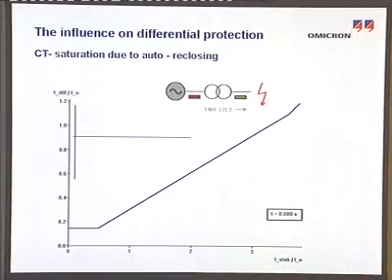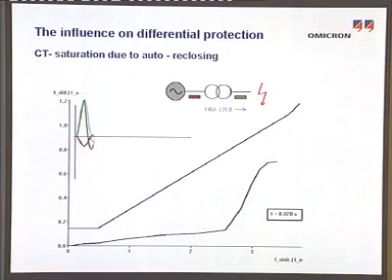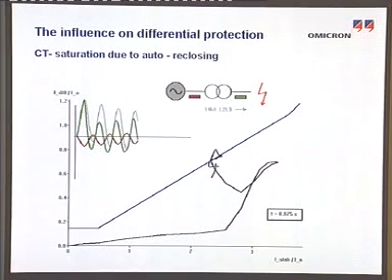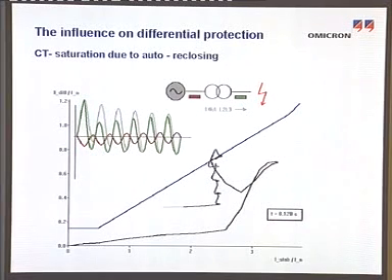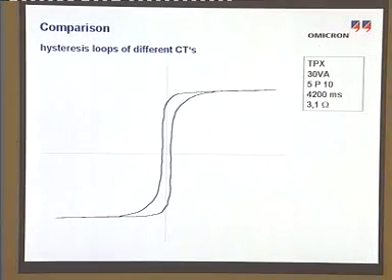If the relay behavior is also examined offline at re-closure, the simulation shows that the stabilizing characteristic is exceeded in the second area due to smaller stabilizing currents and considerably lower rise. Consequently, tripping of the differential protection is to be expected. Therefore, the iron-core CT does not meet the requirements for this specific application if it is supposed that the tripping characteristic cannot be set to be less sensitive.